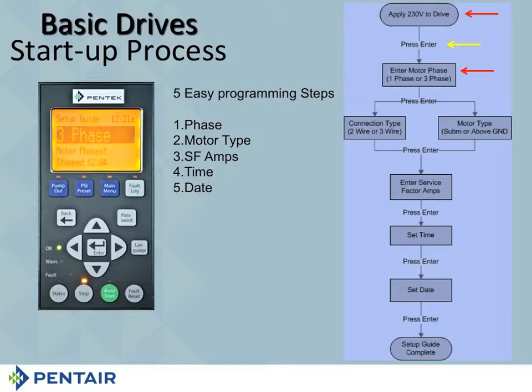You'll notice if you look over at the picture of the screen there, the screen says 3-phase. If you were to hit enter right now, it would mean that you would have a 3-phase motor. So whichever one you pick, you press enter, and that's the one that it chooses. If you pick single phase, it's going to ask you another question, and the question is, are you running a 2-wire motor or are you running a 3-wire motor? If you have picked 3-phase, the second question is going to be, are you running a submersible or are you running an above ground motor? Pick the appropriate answer and then press enter.